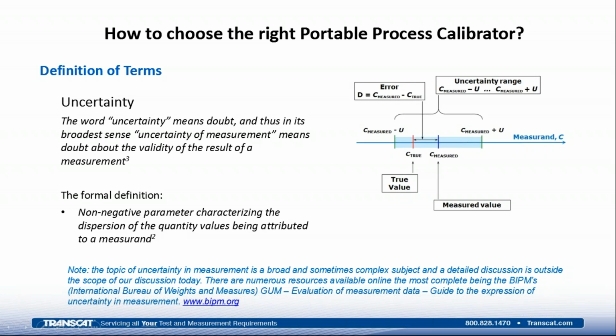A non-negative parameter characterizing the dispersion of the quantity values being attributed to a measurand. So what does this mean essentially? Looking at our graphic, whereas before we had a measured value compared to a true value, which would be the value that we would be using from our calibrator or our standard, that difference for any given particular measurement is defined as the error. But there's uncertainty, or potential uncertainty, about the calibrator being used and the measurement being made. So the uncertainty of that range is the measured value plus or minus that uncertainty.